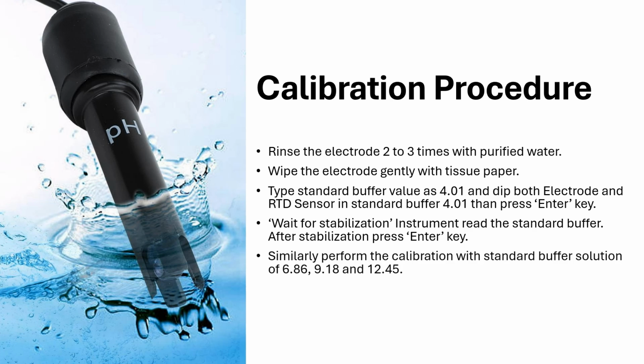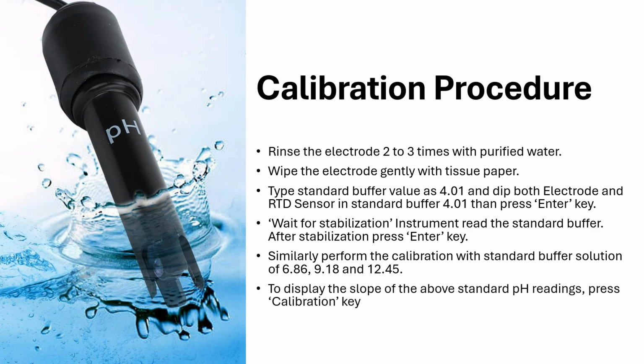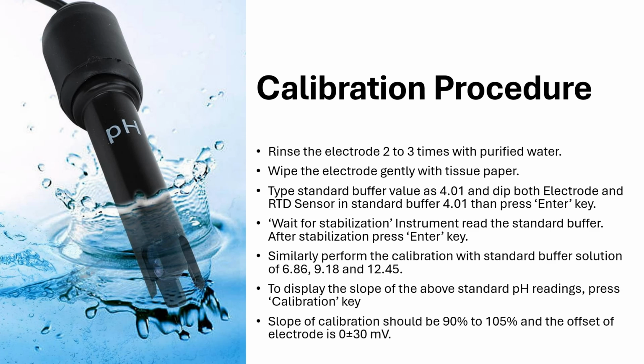Now, in the same way, repeat this calibration process with the remaining standard buffer solutions, that is pH values 6.86, 9.18 and 12.45, right? After calibration with all the buffer solutions, press the calibration key to display the slope of the calibration reading. This slope reflects the accuracy of the calibration, right? For accurate calibration, the slope should be between 90 to 105% and the offset of the electrode should fall within plus or minus 30 millivolts. If the slope or offset falls outside these ranges, out of calibration should be initiated, right?